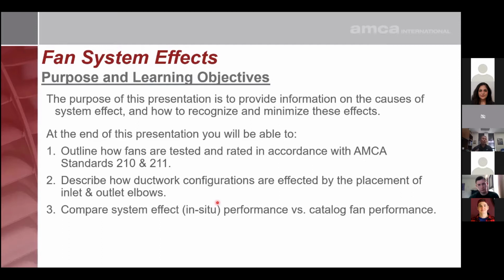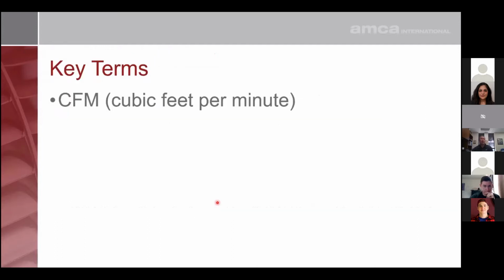What we're going to talk about is how fans are tested and rated, and how ductwork configurations change fan performance and why. Then we're going to watch a video of an actual fan in operation, where we can add ductwork to it, take ductwork off, and see how it changes fan performance. Before we get started, let's first define a few key terms, and there are 3 key terms. The first is CFM, or the volume of air that the fan moves in terms of cubic feet per minute.